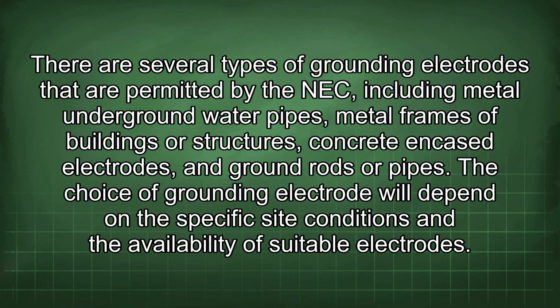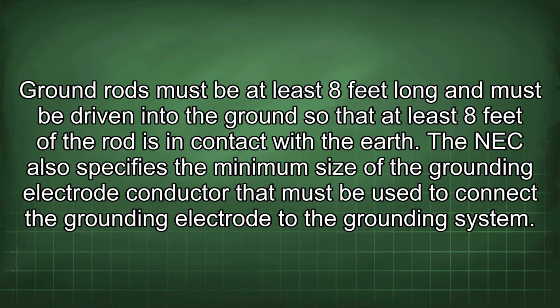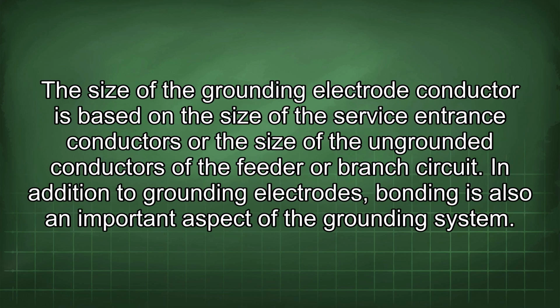There are several types of grounding electrodes that are permitted by the NEC, including metal underground water pipes, metal frames of buildings or structures, concrete encased electrodes, and ground rods or pipes. The choice of grounding electrode will depend on the specific site conditions and the availability of suitable electrodes. Ground rods must be at least 8 feet long and must be driven into the ground so that at least 8 feet of the rod is in contact with the earth. The NEC also specifies the minimum size of the grounding electrode conductor that must be used to connect the grounding electrode to the grounding system. The size of the grounding electrode conductor is based on the size of the service entrance conductors or the size of the ungrounded conductors of the feeder or branch circuit.